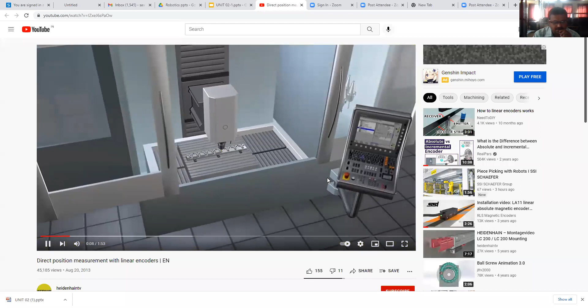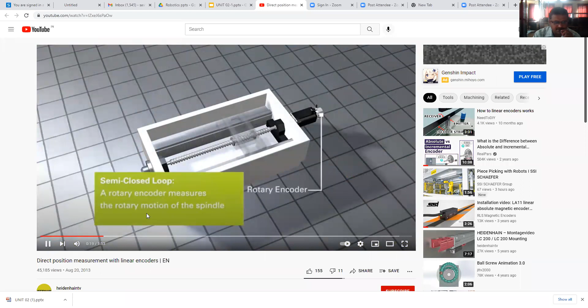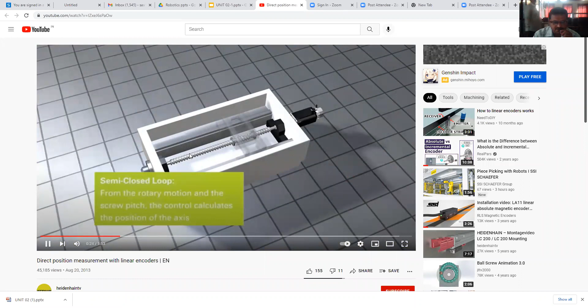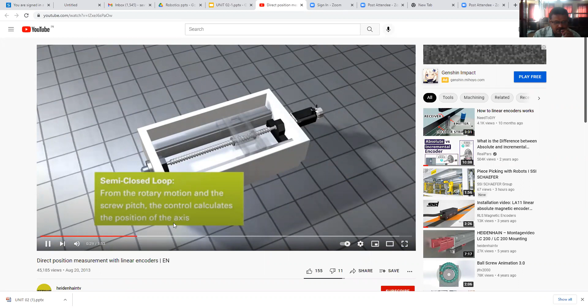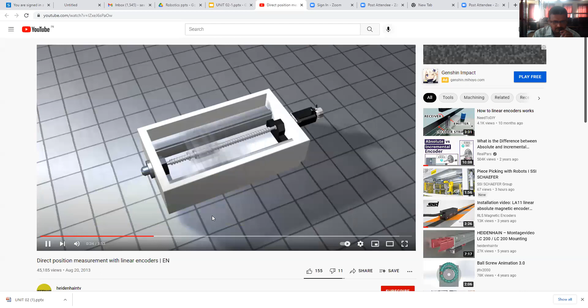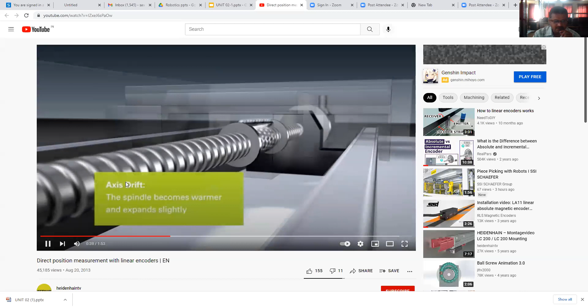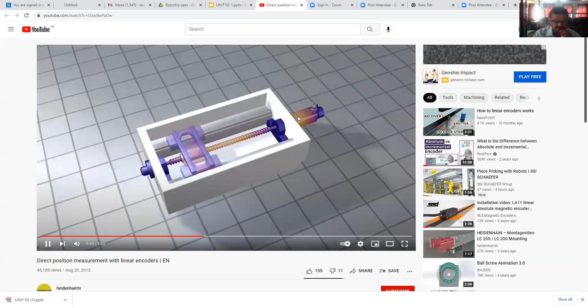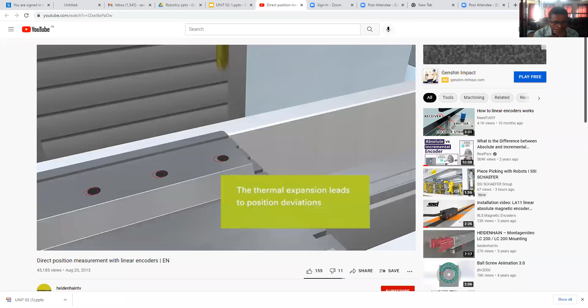Direct position measurement with linear encoders. See that this slide is moving along the screw. Semi-closed loop: the rotary encoder measures the rotary motion of the spindle. This is the rotary encoder. It will measure the rotation of this spindle or screw, and from the rotary motion and the screw pitch, the control calculates the position of the axis. Axis drift: the spindle becomes warmer and expands slightly. That means whenever eccentricity is there, that eccentricity also it will measure. The thermal expansion leads to position deviations.